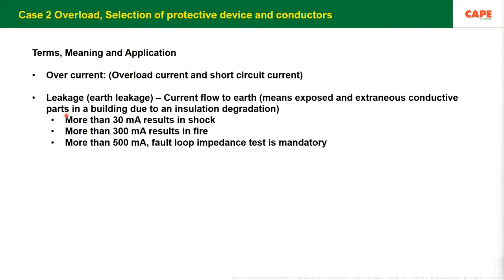Similarly, we have earth leakage. Earth leakage means there is an insulation failure, or degradation in the insulation. As a result, a leakage current flows through the exposed and extraneous conductive parts. Here, you should have an RCD with a tripping current of 30 milliampere, which is necessary to protect against shock. 300 milliampere is required to protect against fire, and if you have a device of less than 500 milliampere in your electrical installation, you don't need to test the fault loop impedance.